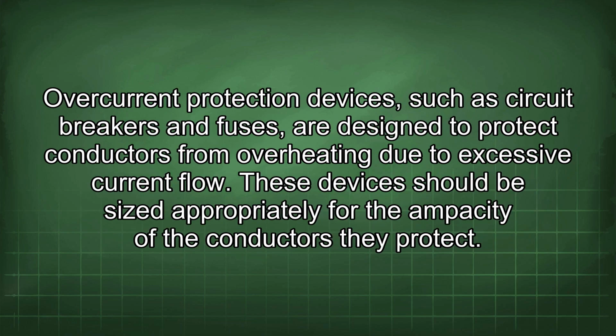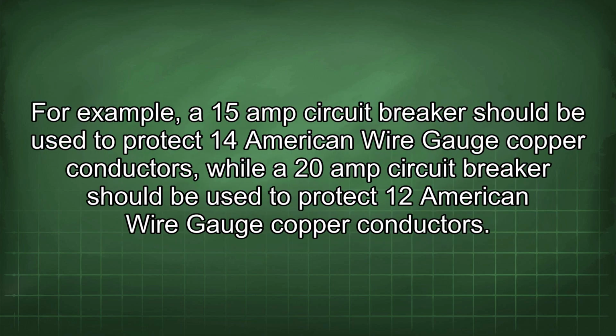Overcurrent protection devices, such as circuit breakers and fuses, are designed to protect conductors from overheating due to excessive current flow. These devices should be sized appropriately for the ampacity of the conductors they protect. For example, a 15 amp circuit breaker should be used to protect 14 American wire gauge copper conductors, while a 20 amp circuit breaker should be used to protect 12 American wire gauge copper conductors.